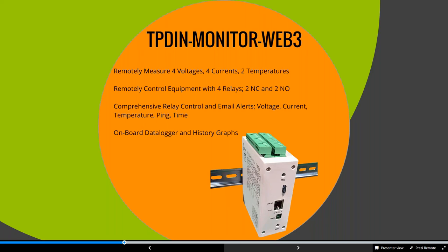With compound logic you can shut off relays based on voltage, current, temperature, ping, or time. You could say: turn on and off a pump at this time, or turn a light on and off, or save power by turning off a camera during certain hours when security is on site. You can do all of that remotely through web or SNMP. We have a free Tycon Systems app to control all your TP-DIN monitors. If you have an issue at the site, our onboard data logger history graph lets you see when you're getting solar power, wind, and evaluate what's going on.